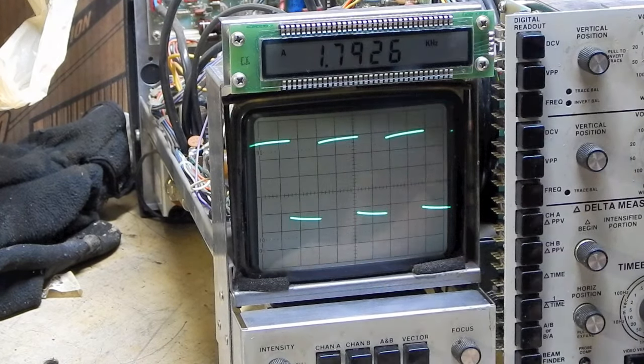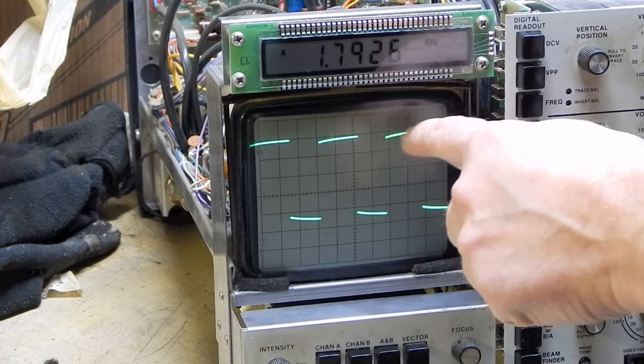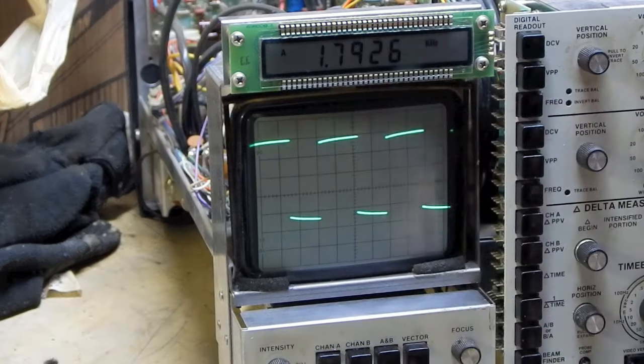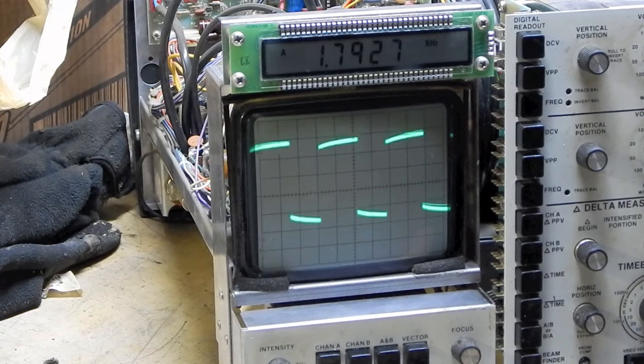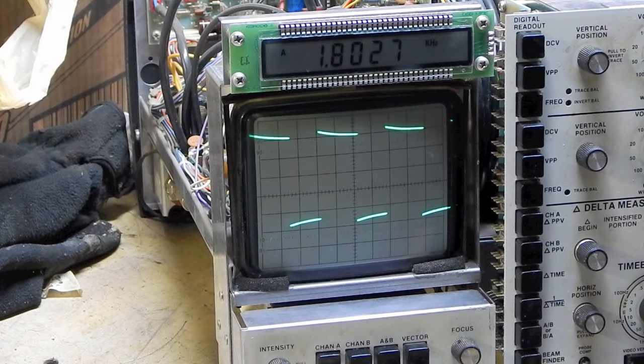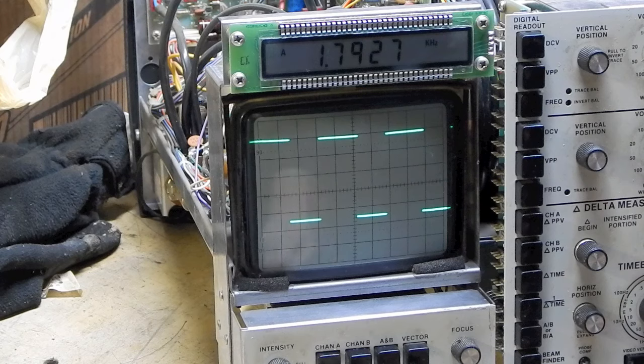And so now I got a nice clean looking waveform and I can adjust the compensation here. And what I'm looking at is the leading edge of the waveform. If you look at the top of the square wave, it's kind of slanted, and if I adjust the compensation, you can see that it goes down. Go the other way, it goes up. And what I want is for it to be as square as possible, like right there. Okay, and it looks pretty good. So it's not perfect.